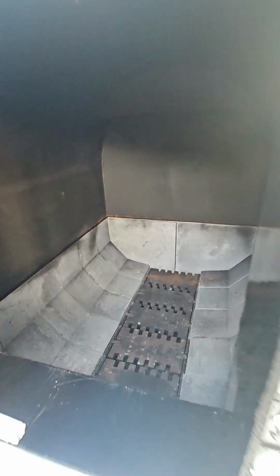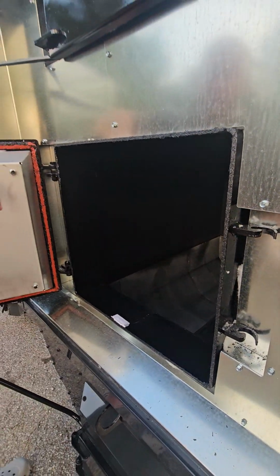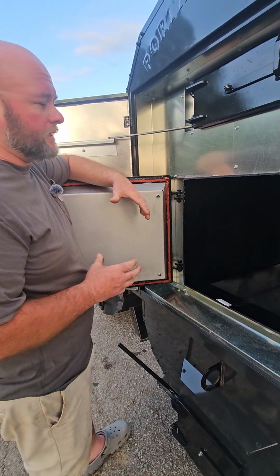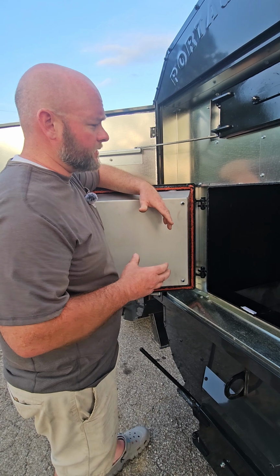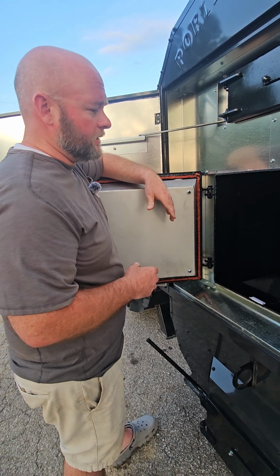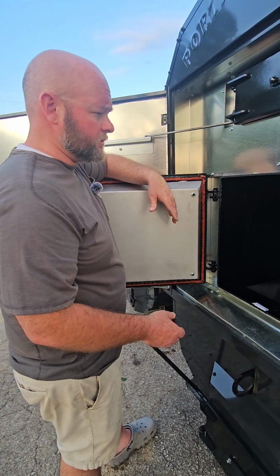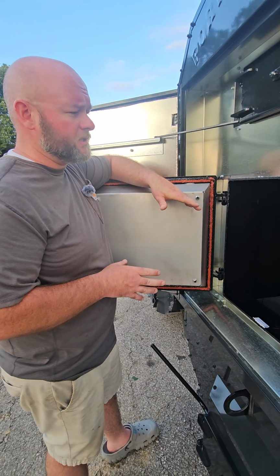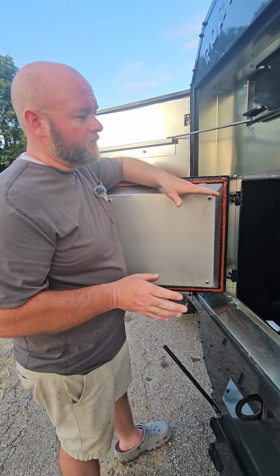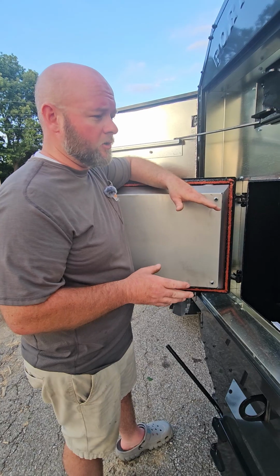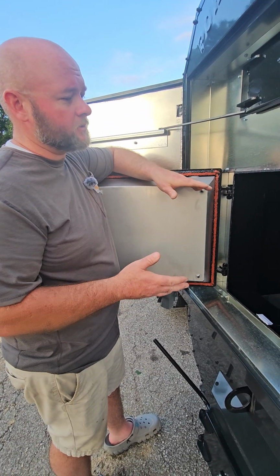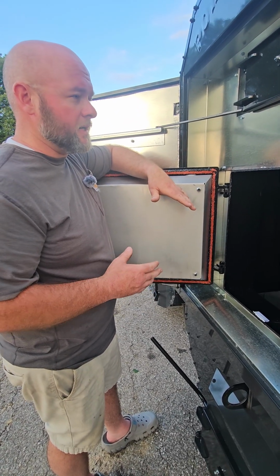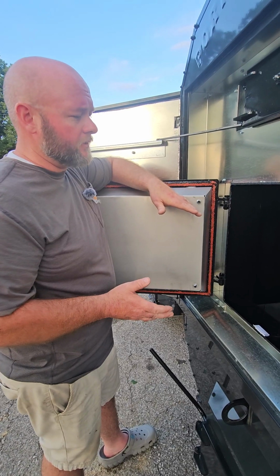What happens is, even on those 409 stainless models, is ash line corrosion. It gets moisture out of your wood and just holds it there in that ash, and it's going to cause what they call ash line corrosion. That's a big problem in these boilers. This boiler is a two-piece boiler, so if you ever have a problem, you don't have to buy a whole boiler. You can buy just the water jacket. So this is basically the last boiler you would ever need to buy.